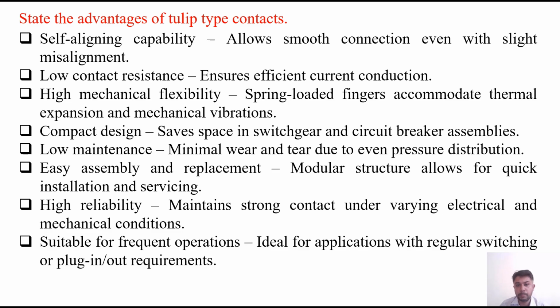High mechanical flexibility. Spring-loaded fingers accommodate thermal expansion and mechanical vibrations. The compact design saves space in switchgear and circuit breaker assemblies, so it is one of the advantages. Low maintenance, because of minimum wear and tear due to even pressure distribution, because the spring pressure is around the radial surface of the contact. Easy assembly and replacement. The modular structure allows for quick installation and servicing. High reliability. They maintain strong contact under varying electrical and mechanical conditions. Suitable for frequent operations. It is ideal for applications with regular switching or plug-in and plug-out requirements, as per the application or operational condition. So these are several advantages of tulip type contacts of circuit breakers.